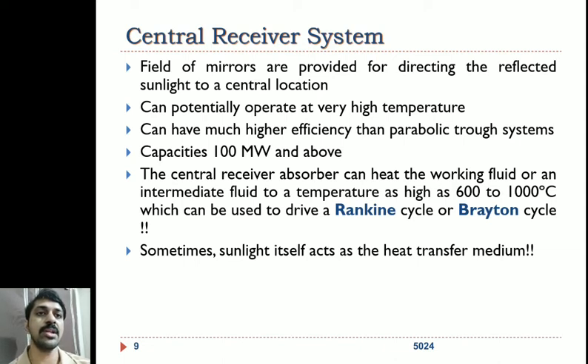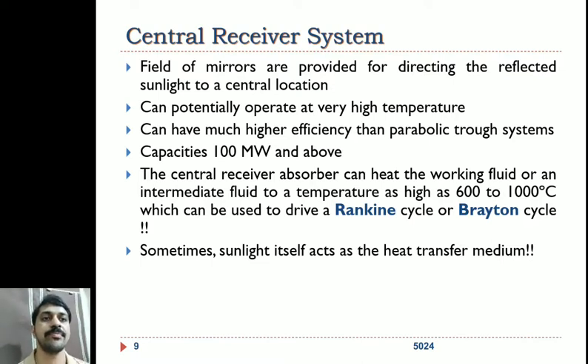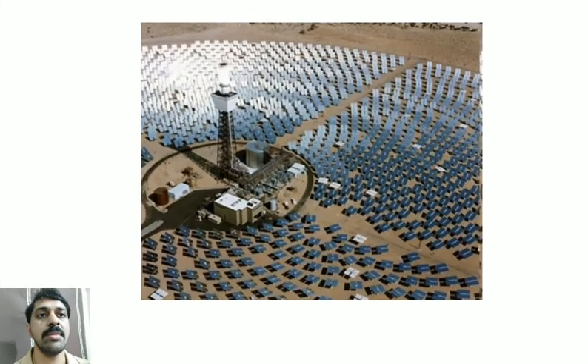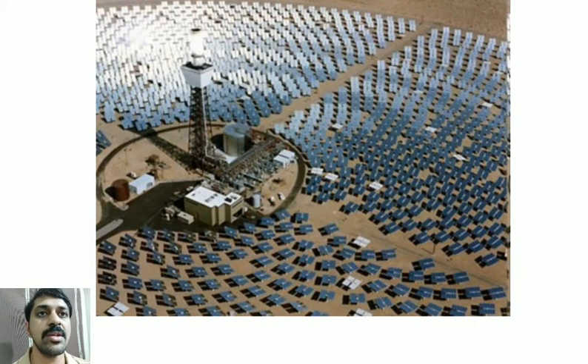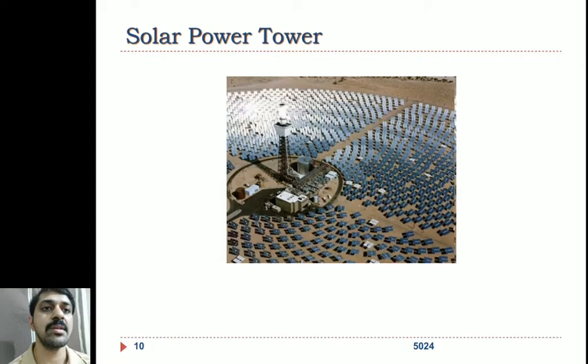The field of mirrors directs reflected sunlight to a central location. The central receiver can potentially operate at very high temperatures and at capacities of 100 megawatts and above. The absorber can heat the working fluid to temperatures as high as 1000 degrees Celsius, which can be used to drive a Rankine or Brayton cycle. Sometimes sunlight itself acts as the heat transfer medium. A photograph of a solar power tower shows the large number of mirror segments used. Large space requirements are a major disadvantage, but where space and initial investment are not concerns, megawatts of electricity can be generated.